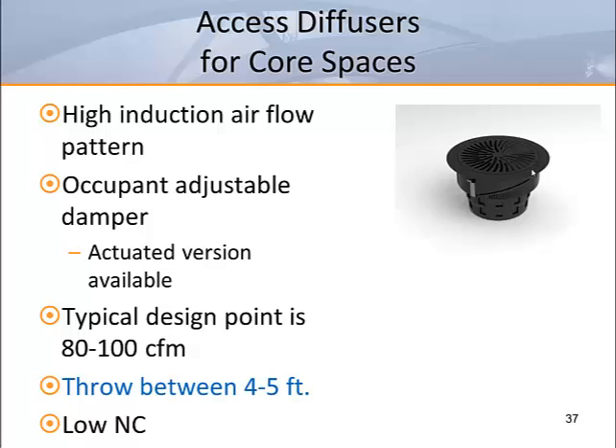The products specified in core areas for underfloor projects are typically small round or rectangular outlets to be located near the occupant's work area. These diffusers have a high induction swirl airflow pattern and can be manually adjusted or actuated. The typical design point for this style of diffuser is 80 to 100 CFM with throws to 50 feet per minute limited to 4.5 feet above the floor height. They are typically operated at plenum pressures of less than 1/10 of an inch and have low NC levels.